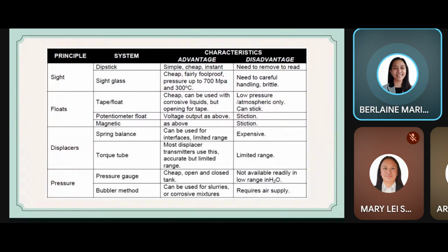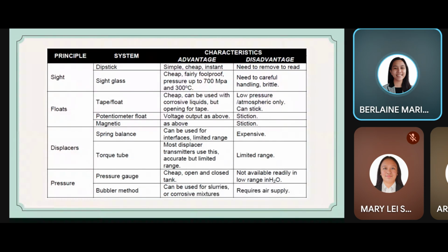Sa pressure methods naman po is ang pressure gauge, which is cheap and can be used in both open and closed tanks, which makes it versatile. But it is not available in low ranges of water pressure, meaning it cannot measure very shallow levels accurately. Sunod naman po is bubbler method, which works well for slurries and corrosive mixtures because the measuring device does not come in contact with the liquid. Its disadvantage is that it needs a constant air supply, which adds extra costs and maintenance.